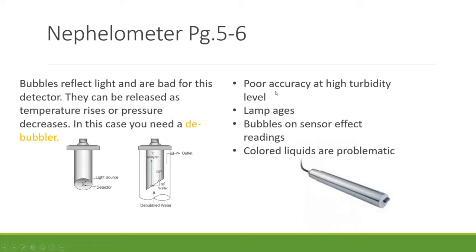Specific issues with nephelometers include poor accuracy at high turbidity levels, lamp aging (common to all technologies), bubbles on the sensor affecting readings, and colored liquids being problematic. One of the devices we'll discuss is well suited for colored liquids, and another for high turbidity levels. There's a table in the ILM that summarizes applications for all types on one page.